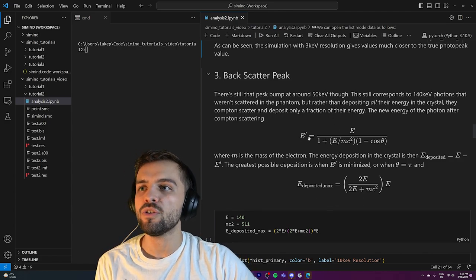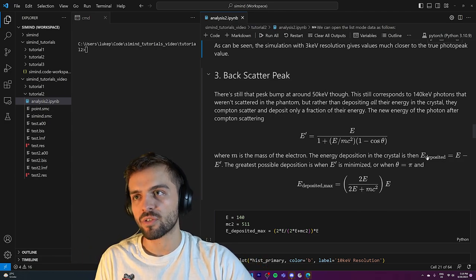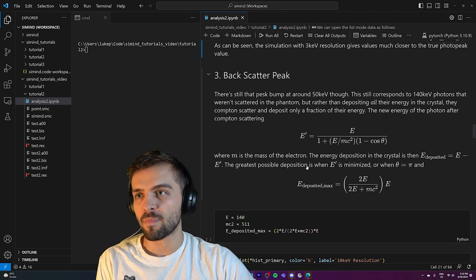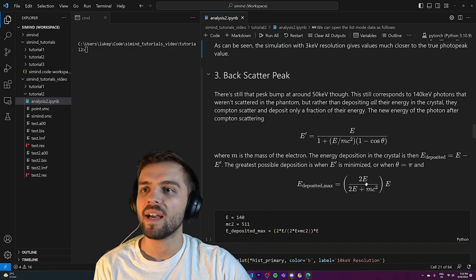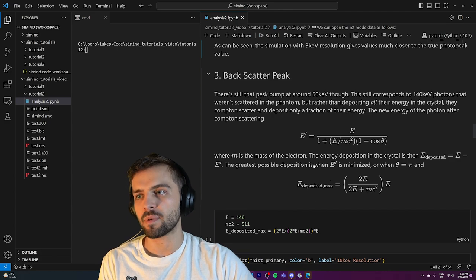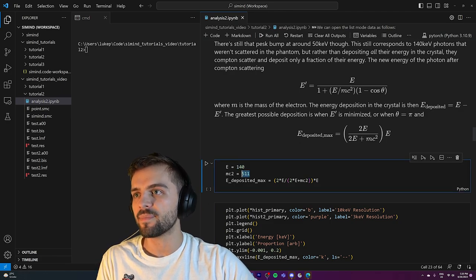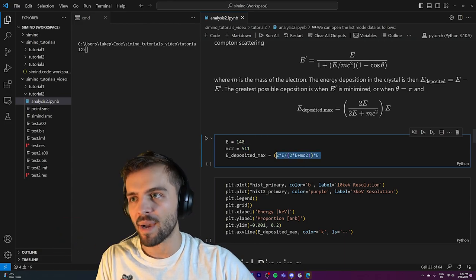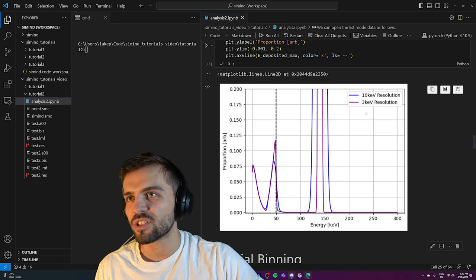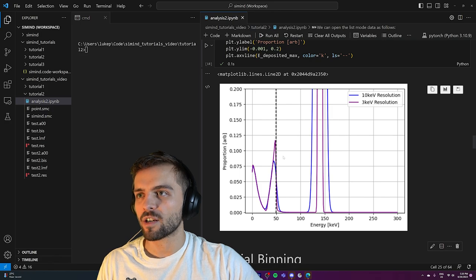What does the backscatter peak correspond to? These are 140 keV photons that don't deposit all their energy in the crystal — they scatter outwards through Compton scattering, depositing only a fraction of their energy. The Compton scattering formula gives the new energy of the photon as: E_new = E_old / (1 + (E_old/mc²)(1 - cosθ)), where θ is the scattering angle. The energy deposited in the crystal equals the original energy minus the new photon energy. When θ = π, the maximum deposited energy via Compton scattering is 2E / (2E + mc²) × E. With E = 140 keV and mc² = 511 keV, this gives our theoretical maximum backscatter energy, which aligns with the observed peak around 50 keV.